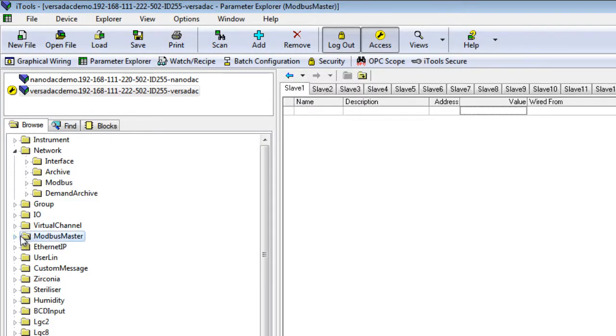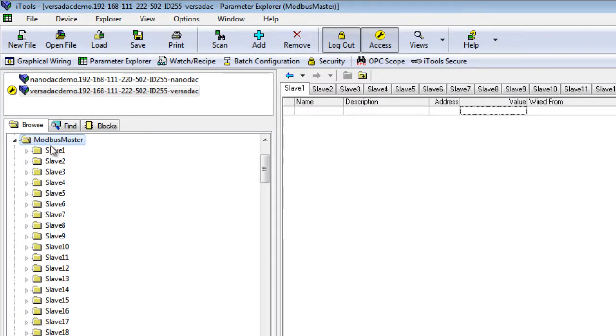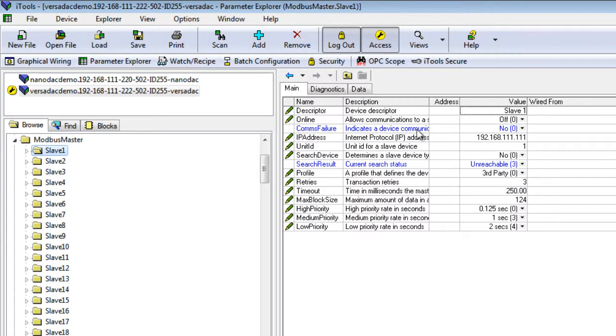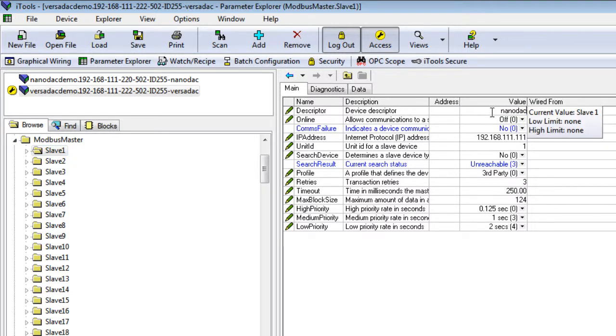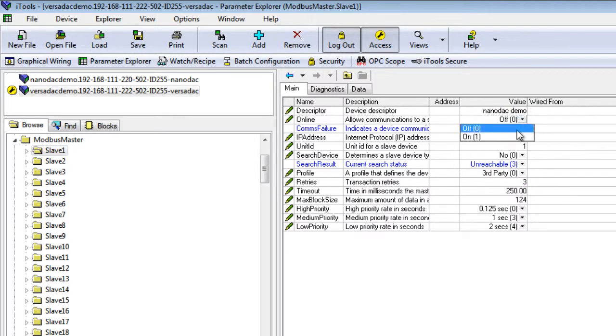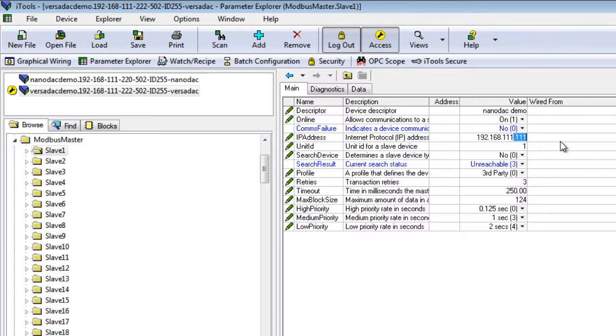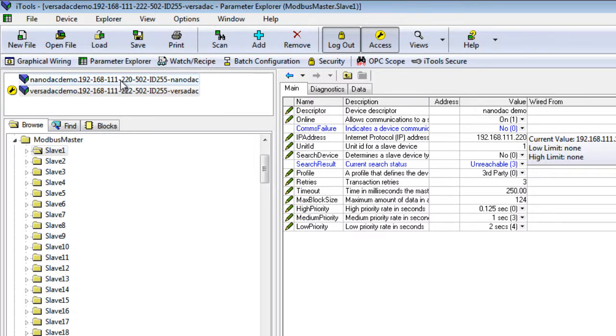Set up Slave 1, rename as Nanodac Demo or a suitable name. Change Online to On. Edit the IP address to match the instrument to connect the Versadac to. You can always read this from the Connected Instruments panel.